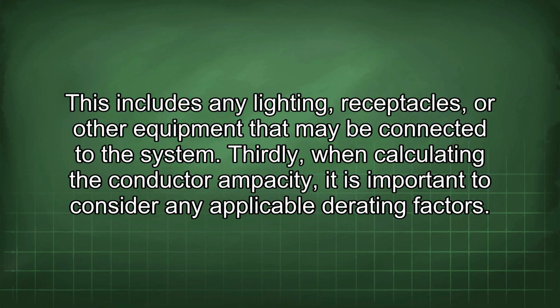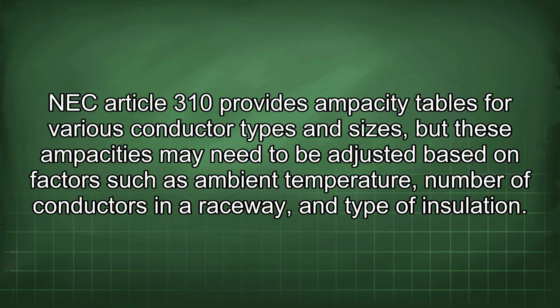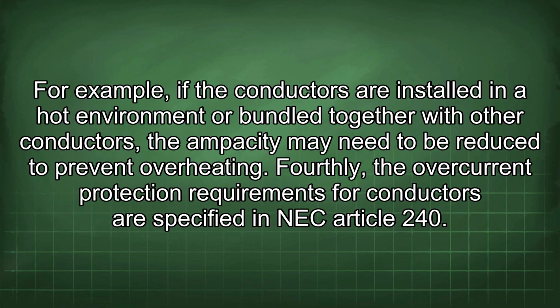Thirdly, when calculating the conductor ampacity, it is important to consider any applicable derating factors. NEC Article 310 provides ampacity tables for various conductor types and sizes, but these ampacities may need to be adjusted based on factors such as ambient temperature, number of conductors in a raceway, and type of insulation. For example, if the conductors are installed in a hot environment or bundled together with other conductors, the ampacity may need to be reduced to prevent overheating.